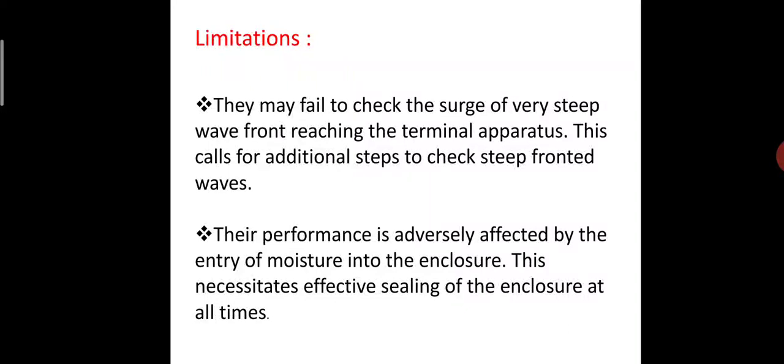And limitations. They may fail to check a surge of very steep wavefront reaching the terminal apparatus. This calls for additional steps to check steep-fronted waves. Their performance is adversely affected by the entry of moisture into the enclosure. This necessitates effective sealing of the enclosure at all times.